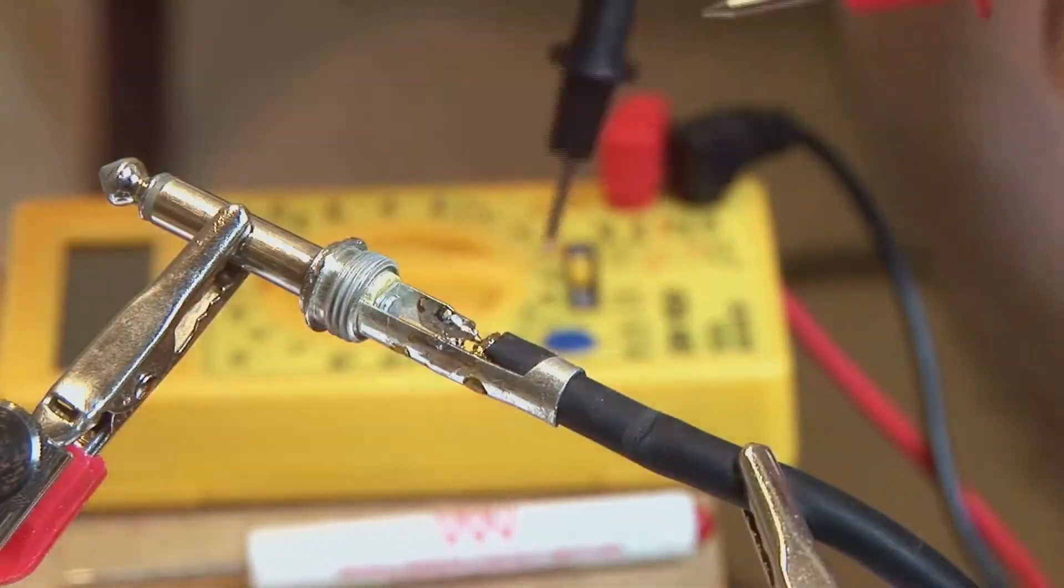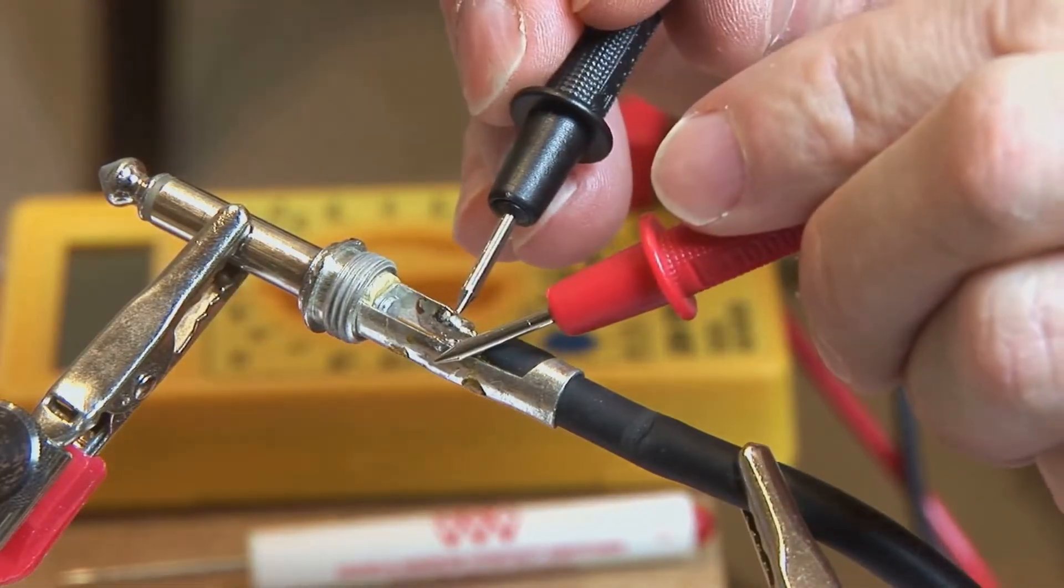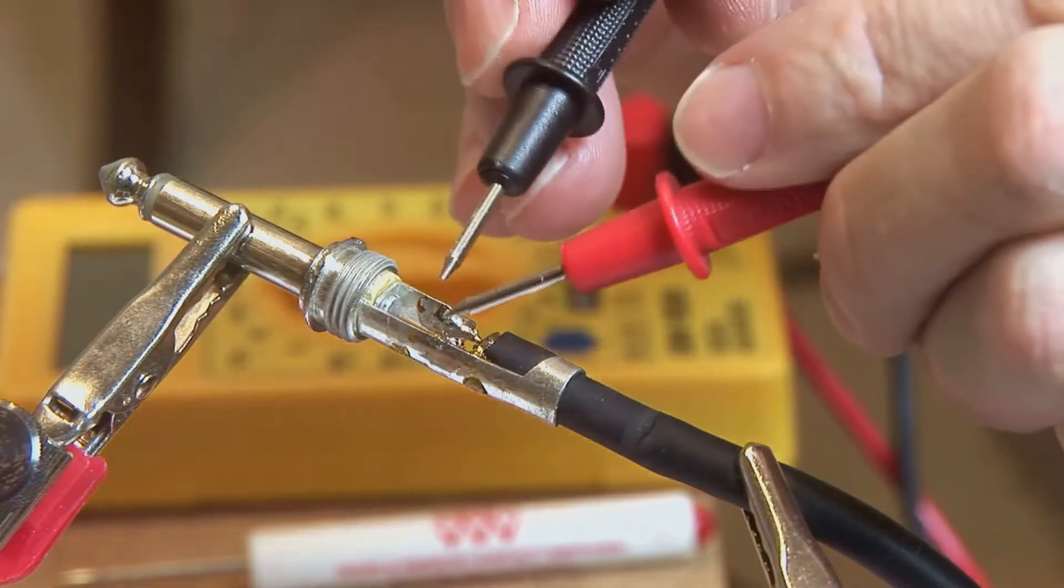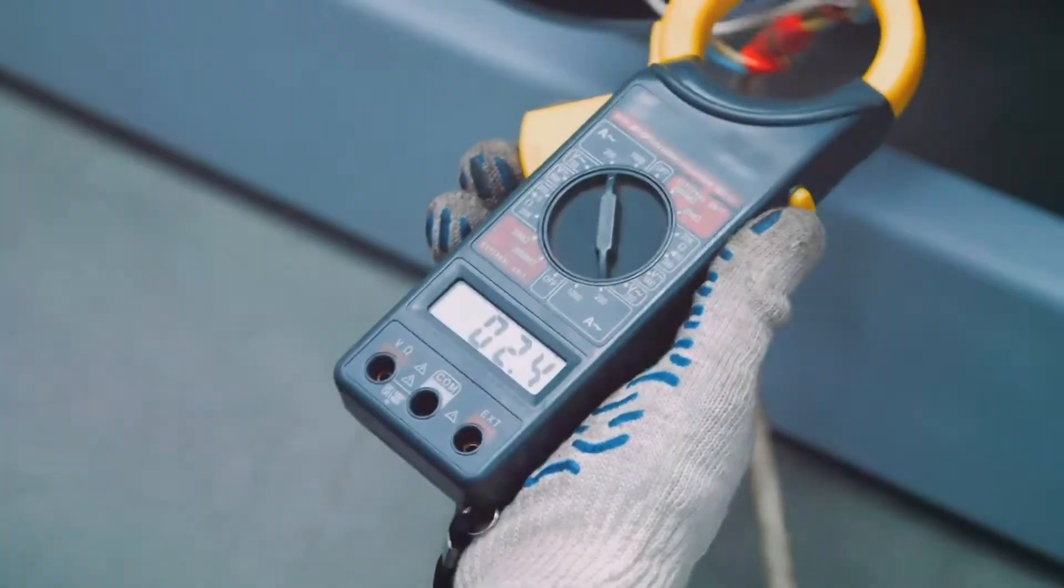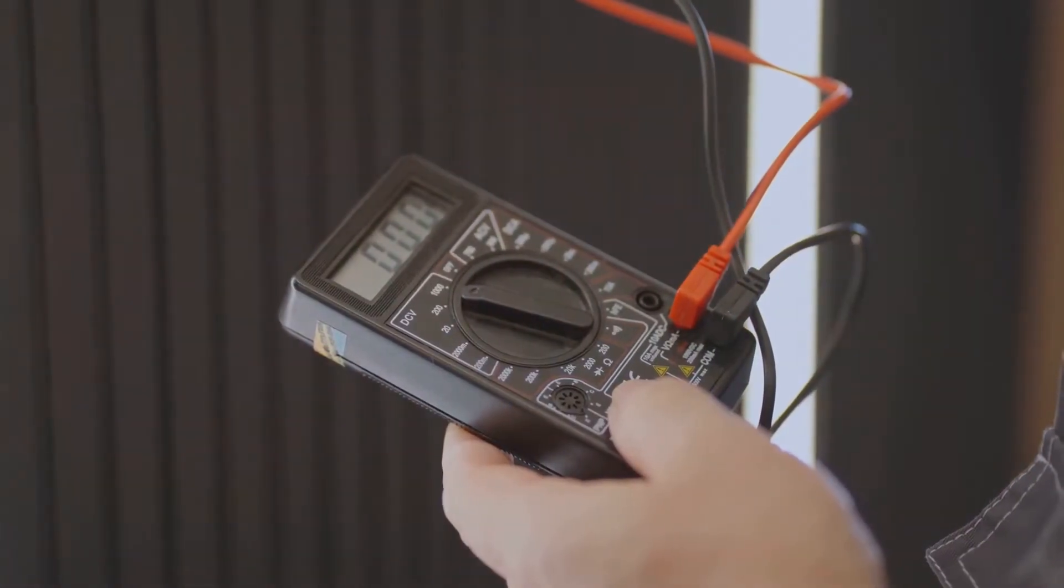Next, touch one probe to each terminal - it doesn't matter which probe goes on which terminal. Now read the display on your multimeter. This number is the solenoid's resistance measured in ohms. Write down this reading - it's important for figuring out if your solenoid is healthy.